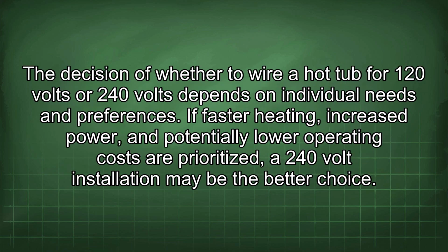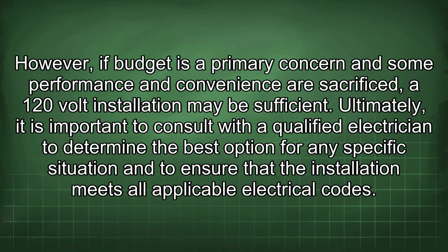The decision of whether to wire a hot tub for 120 volts or 240 volts depends on individual needs and preferences. If faster heating, increased power, and potentially lower operating costs are prioritized, a 240 volt installation may be the better choice. However, if budget is a primary concern and some performance and convenience are sacrificed, a 120 volt installation may be sufficient. Ultimately, it is important to consult with a qualified electrician to determine the best option for any specific situation and to ensure that the installation meets all applicable electrical codes.